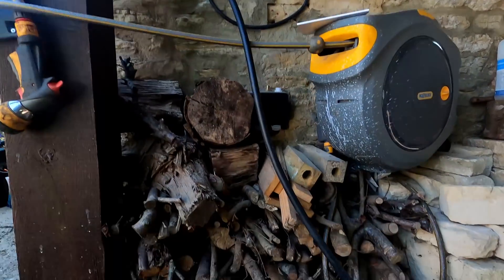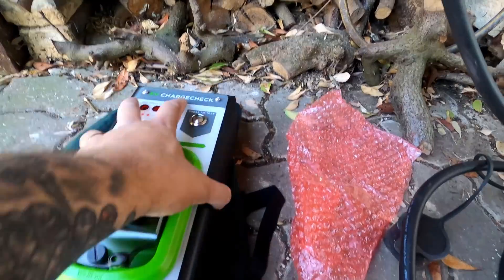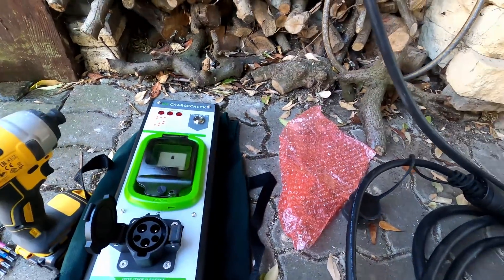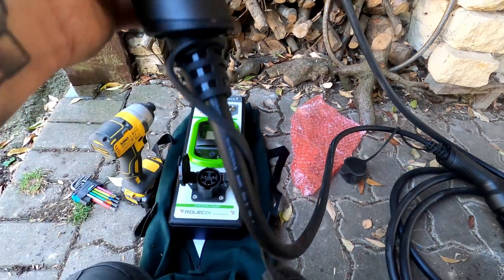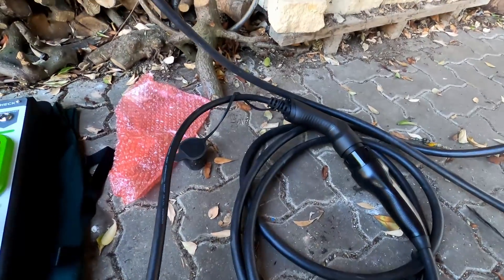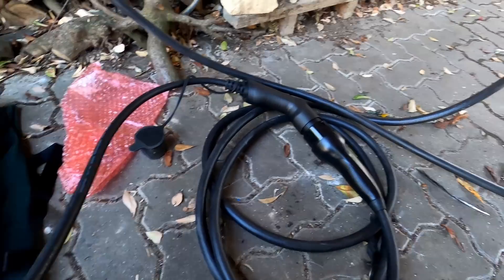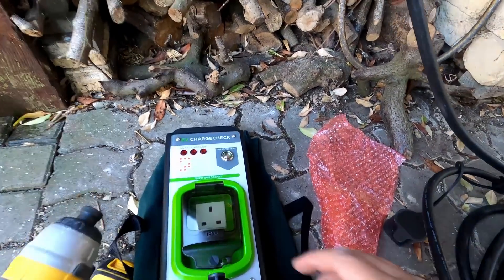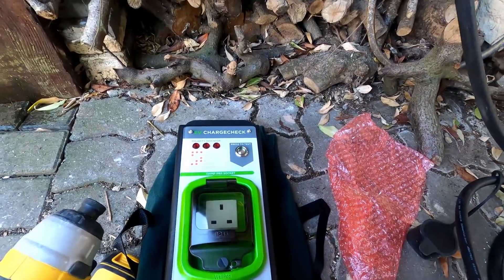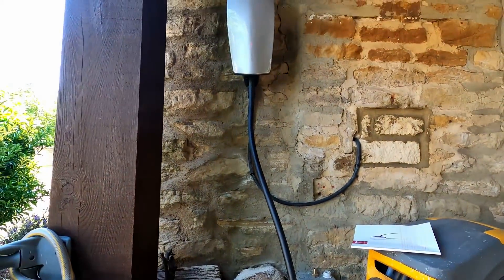The Tesla unit is in and powered up. We've got our Rolec EV charge check - and I have to say for £450 it does feel cheap and nasty, but it serves a purpose. It's a type 1 socket on the front and it comes with the adapter lead that converts from type 1 to type 2. Because the Tesla charger is type 2 we just use the adapter and press the button - the lights should all light up.